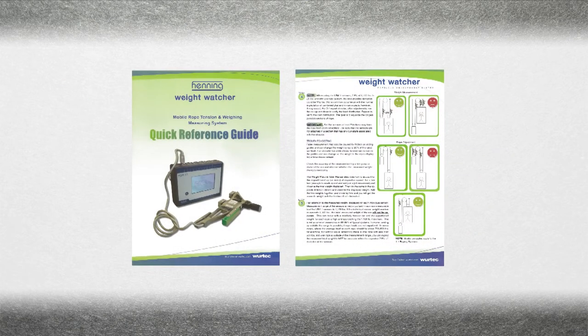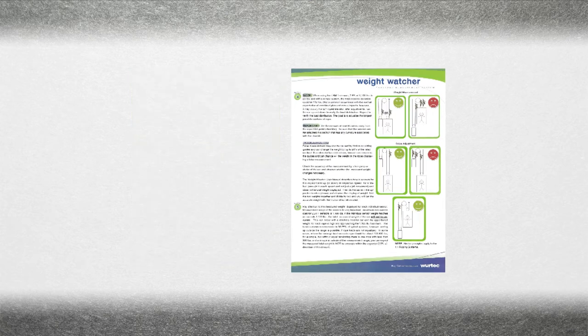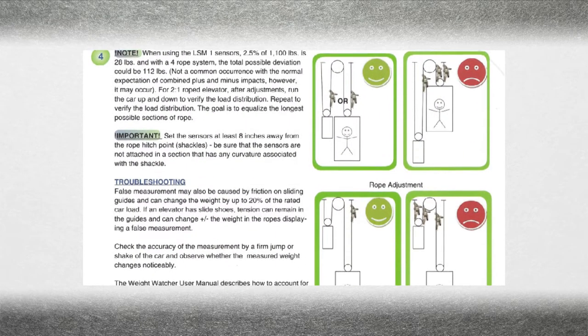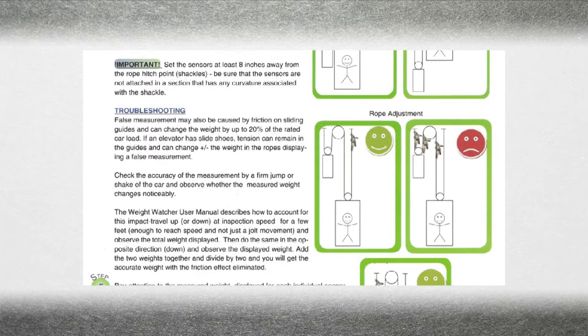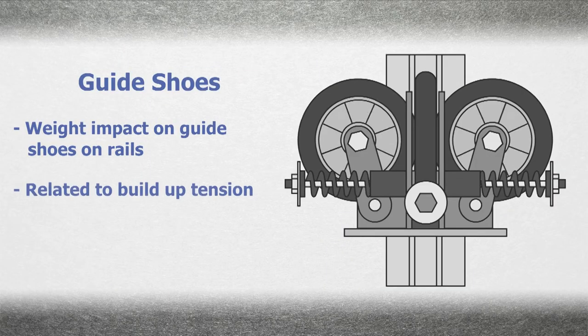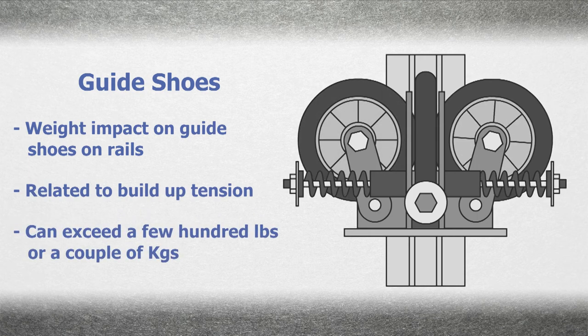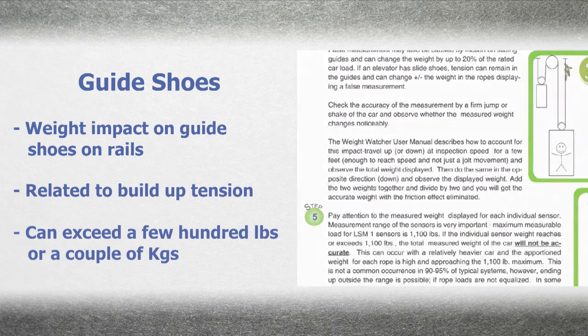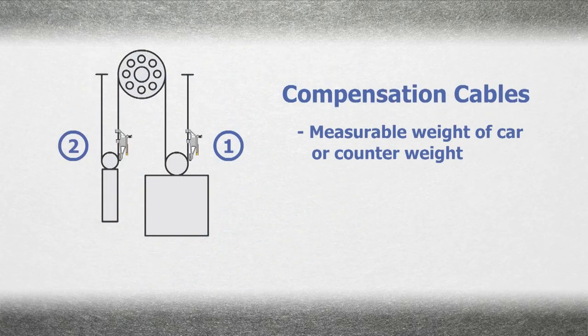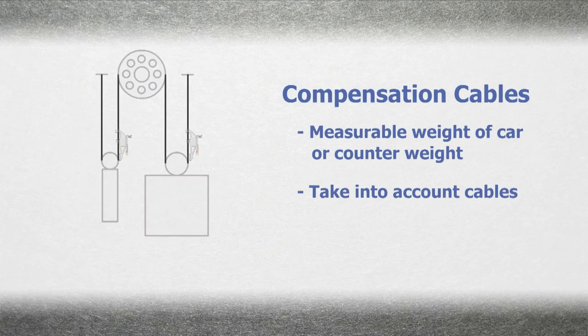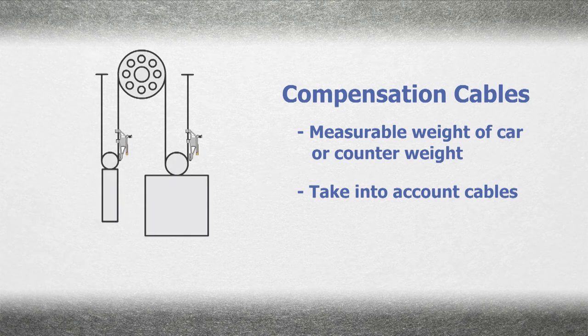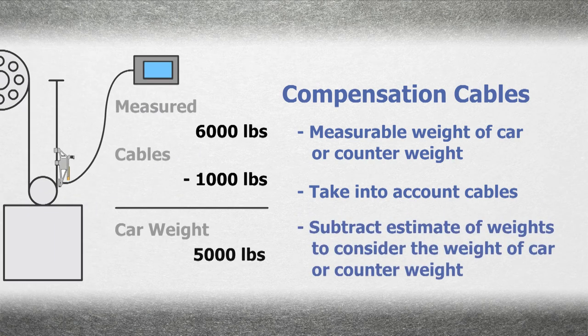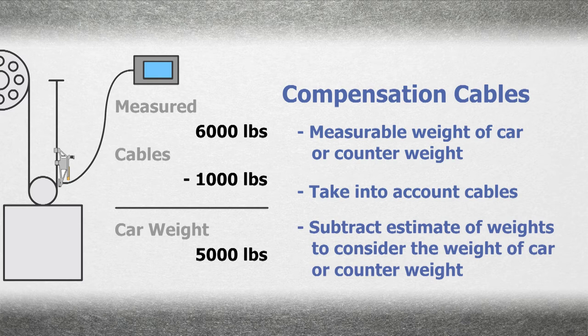For more information about setting sensors and troubleshooting circumstances that may lead to false measurement, refer to Step 4 in the Mobile Weight Watcher Quick Reference Guide PDF. There could also be some weight impact related to built-up tension in guide shoes on rails. This is covered in the troubleshooting section of the guide. When weighing cars or counterweights, you'll want to take into account compensation cables or other comp-related equipment affecting your weight. Subtract a best estimate of such weights to ensure you are only considering the weight of the car or counterweight.